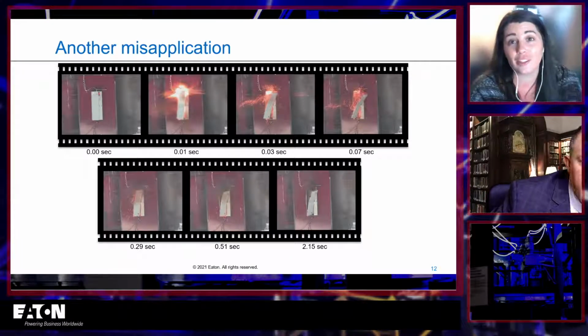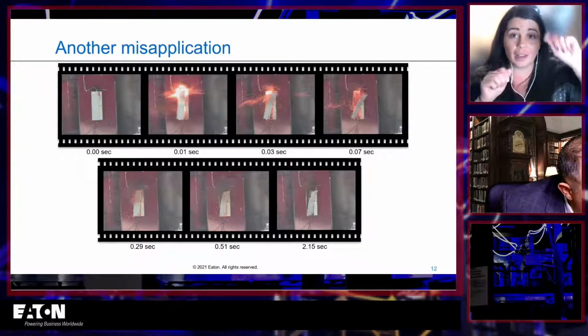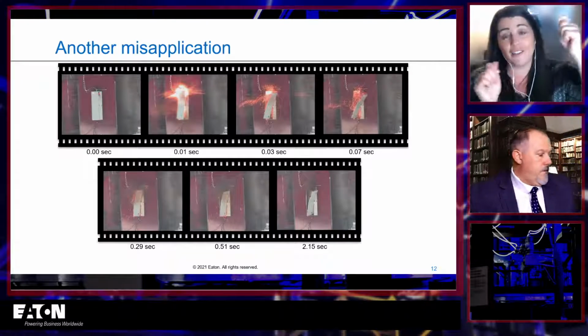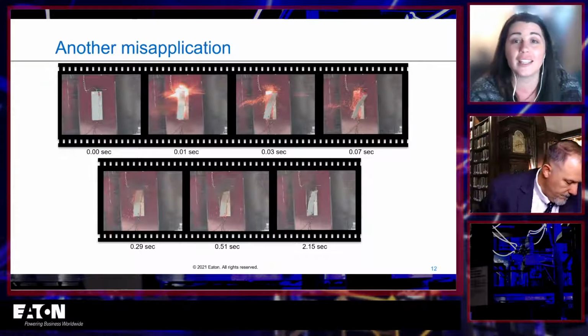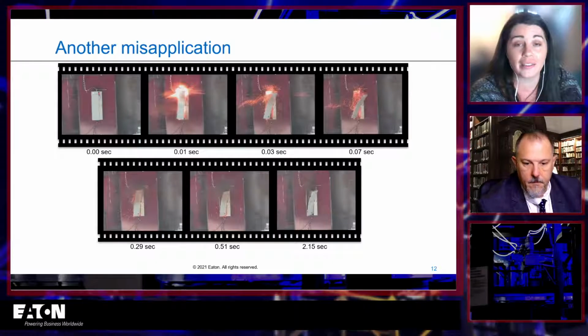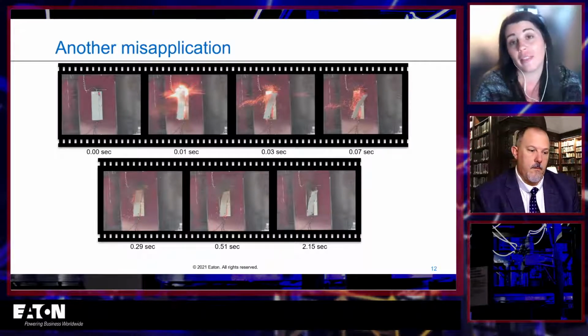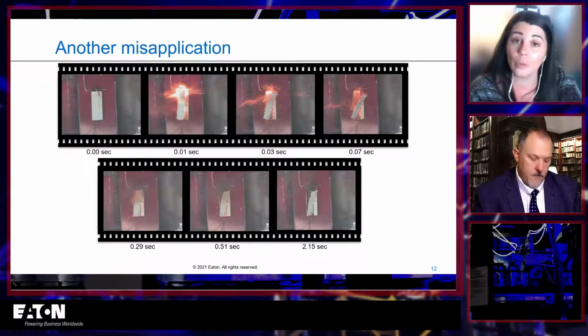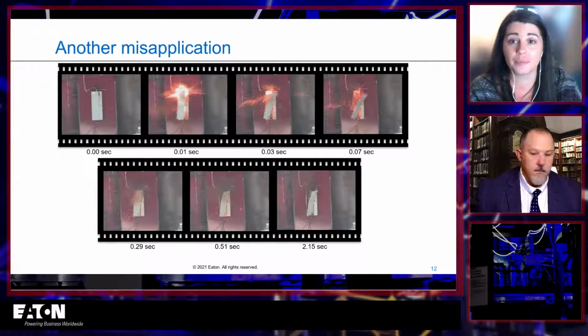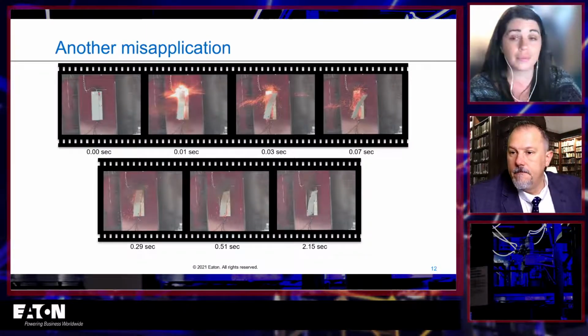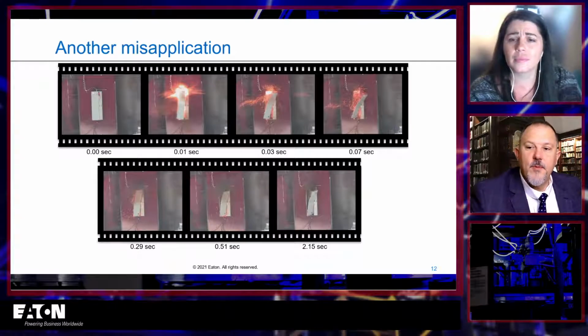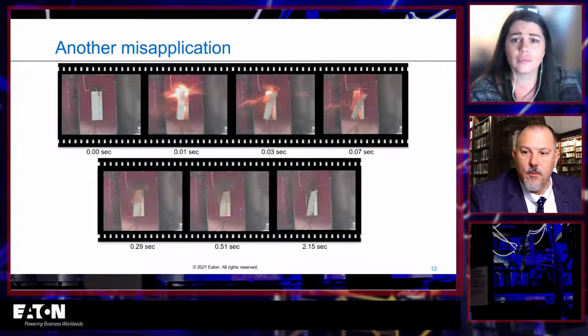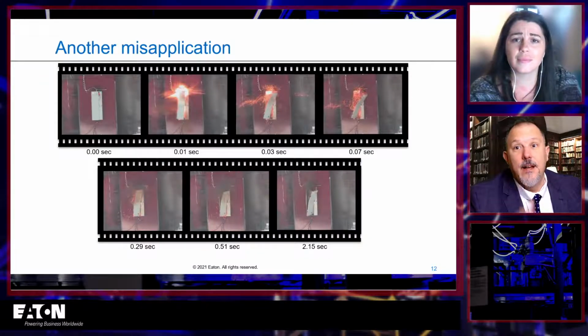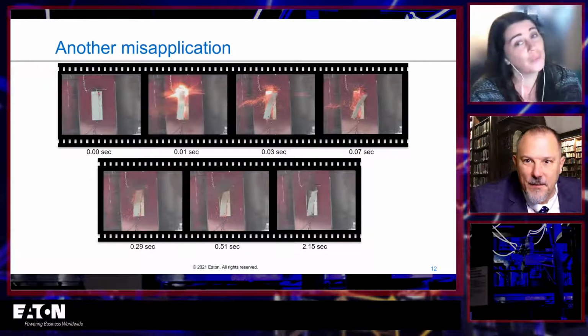And you can always check the continuity between the two. That's the old school way, right? Just check each side and see if you can get power through it. That's the easiest way, if you have none of those other methods of indication, to tell which fuse has opened. Cool. And then if it interrupts below or close to the interrupting rating, can it be reset and used after one time? And I'm sure he's not talking about the fuse itself.